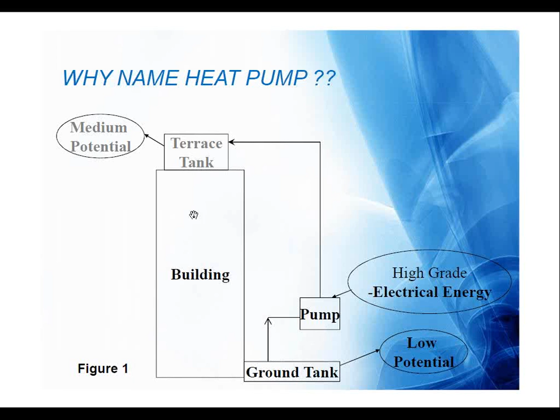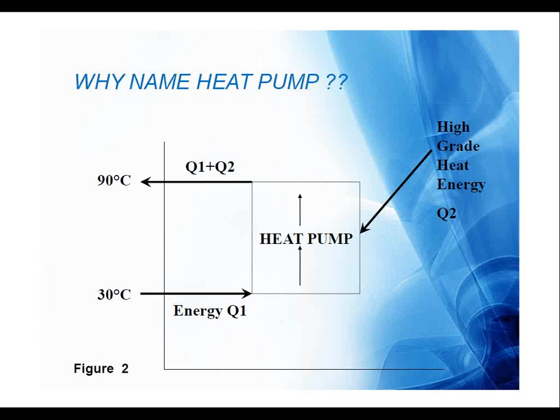This is an application area where we want to have 30-degree water which can be heated up to 90-degree. This is a typical application for all the power plants or the boilers running in a sugar industry, where the condensate which is not coming back to the boiler has to be compensated from the makeup water itself, and the makeup water will be close to around 30-degree, which has to be taken to say 105-degree. Out of this 30 to 105-degree delta T, we can take this 30-degree water into the heat pump, by which we can bring it up to 90-degree, 95-degree with the energy conservation on its evaporator side, which is nothing but the cooling water heat.